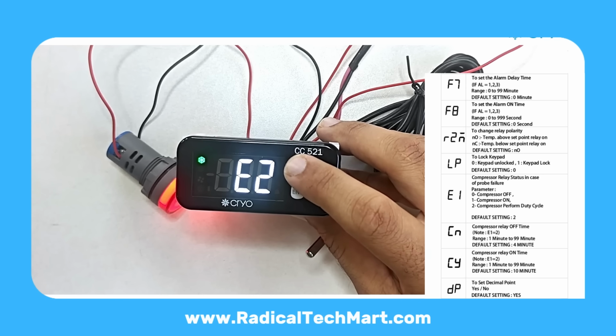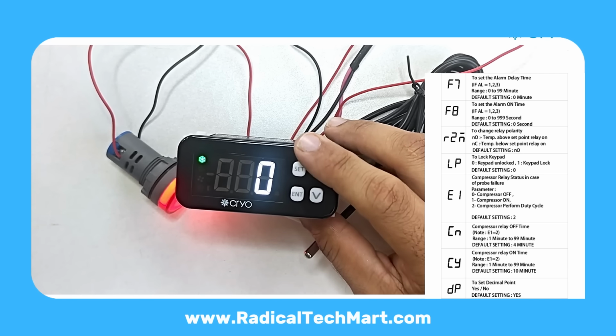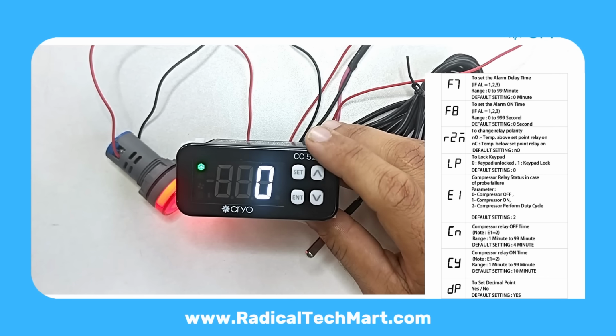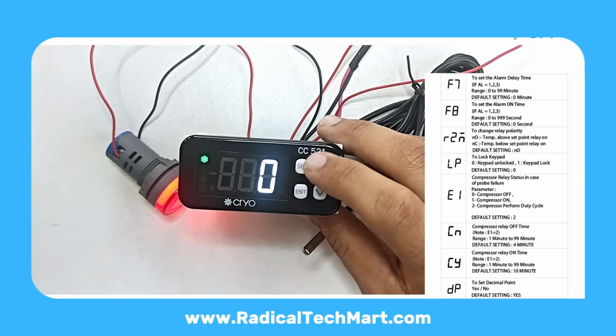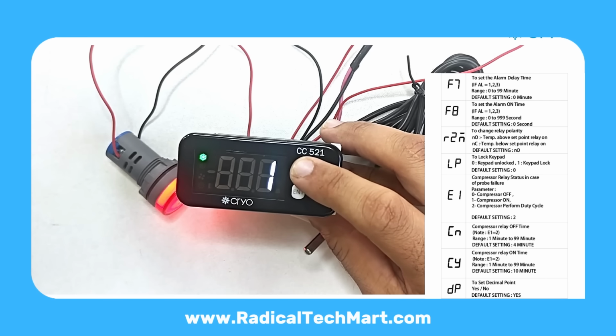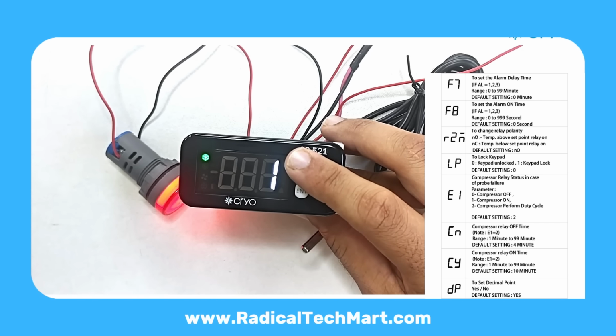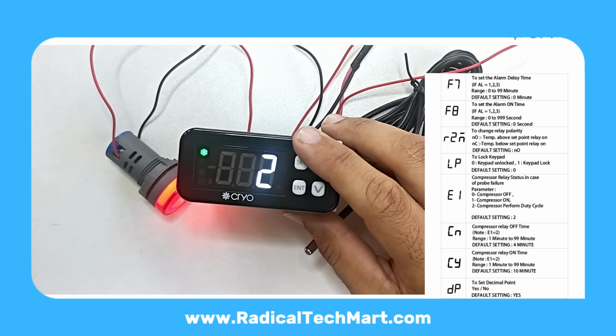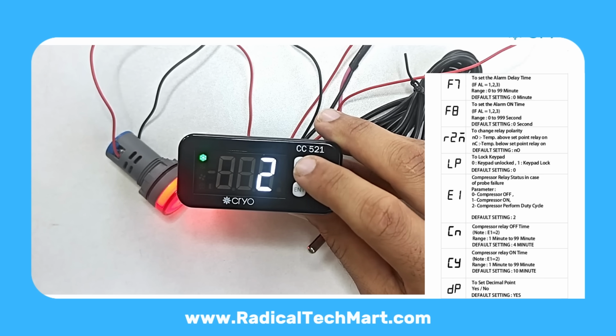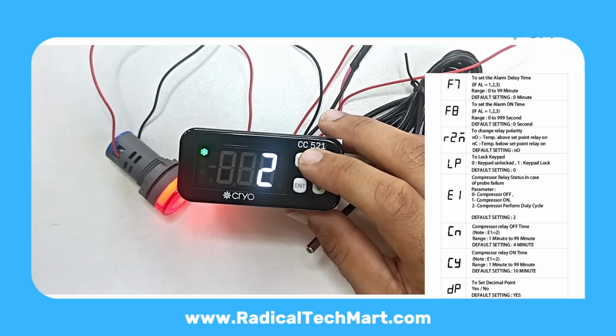Next, E2 Defrost Type. 0 is equal to electrical defrost, compressor off during defrost. 1 is equal to hot gas defrost, compressor remains on. 2 is equal to alternate defrost, compressor cycles on, off based on set point during defrost.